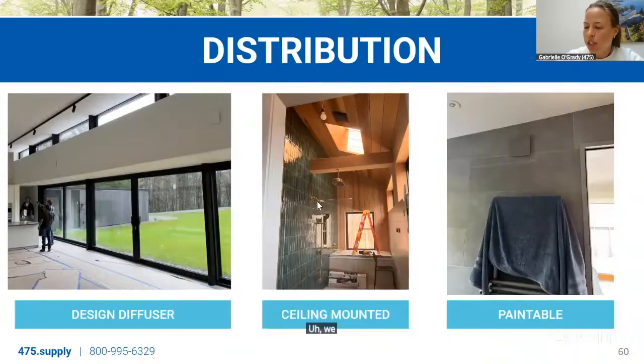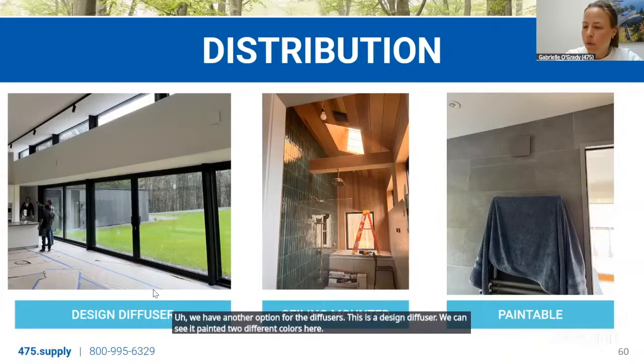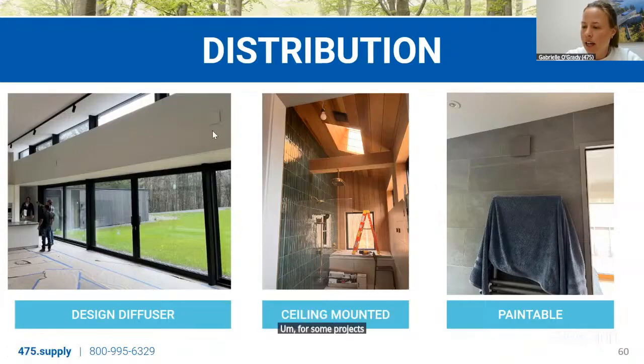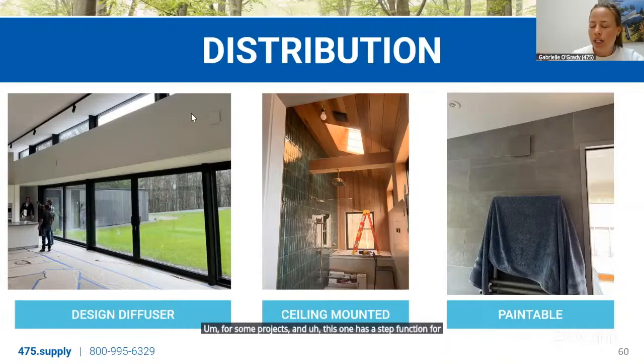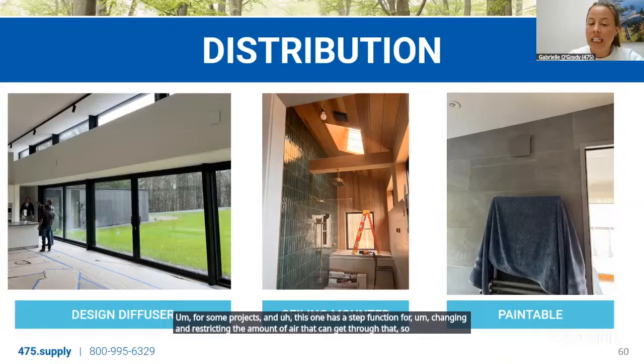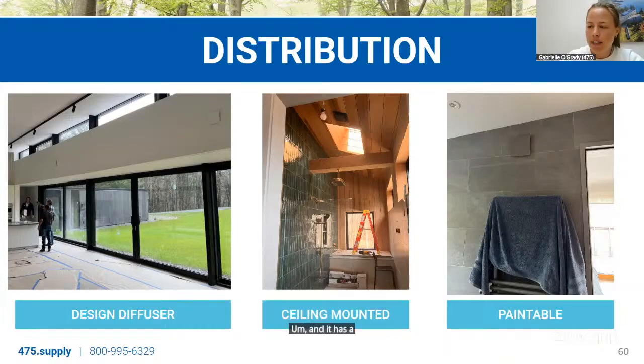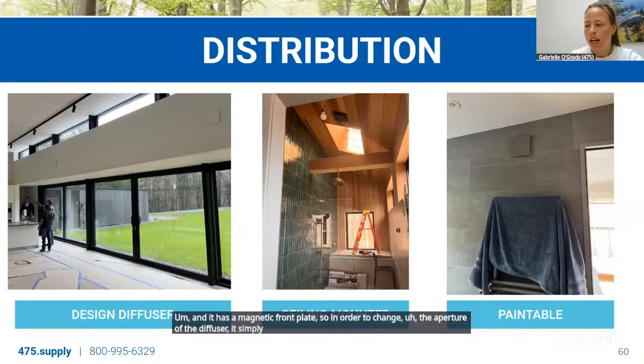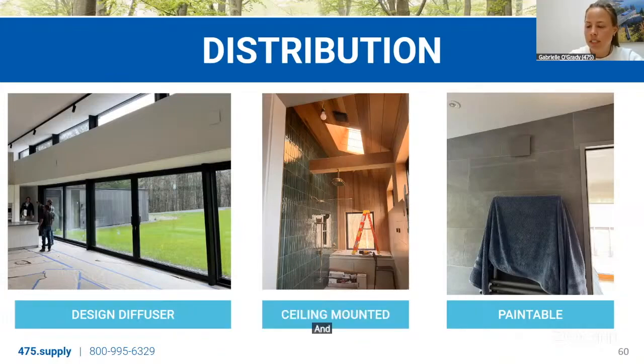We have another option for the diffusers. So this is a design diffuser. We can see it painted 2 different colors here for some projects. And this one has a step function for changing and restricting the amount of air that can get through that. So it allows for very easy commissioning. And it has a magnetic front plate. So in order to change the aperture of the diffuser, you can simply pull that off and snap it back on.